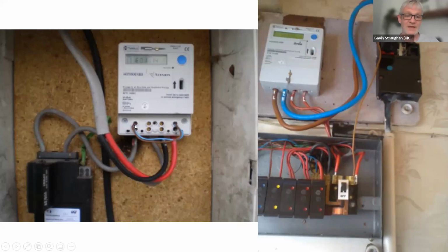Again, same thing here on the left-hand side. And this one, you can see this meter starting to burn. If you look at the size of these tails that go in and out of the meter, they're normally 16mm tails. They're the ones designed to carry that amount of load. The person here has decided to use some 2mm wire to bypass. It's not designed to carry the amount of load that they're consuming at that property. So you can see this screw hole here is already blackened out, where they've moved their wires from this one to the one above, because they've actually melted the meter, because the wires are actually melting.